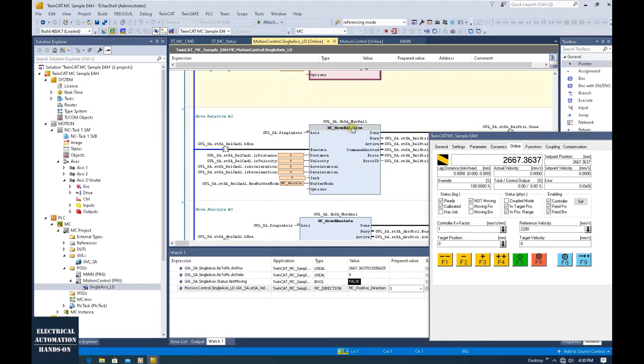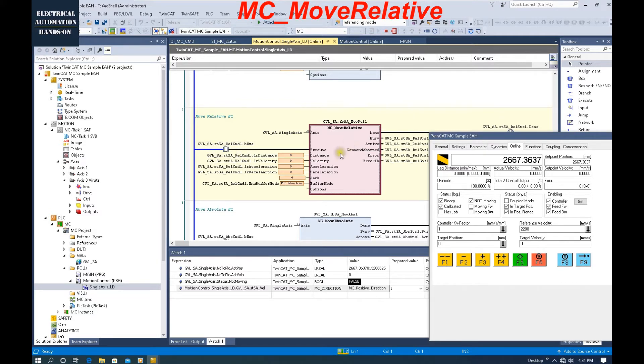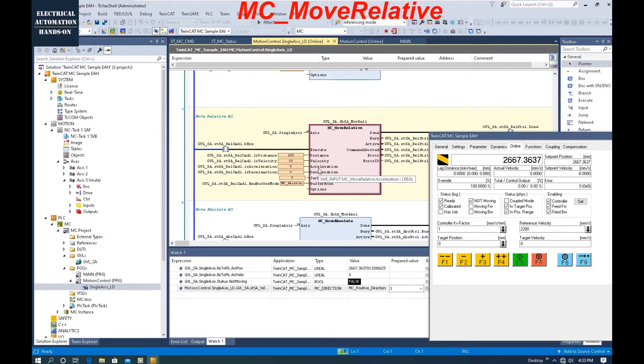Next is Move Relative. Every time we trigger this command, the axis will run a certain distance that we set here. For example, I can set 100, and the velocity I can set very low — for example, 20. Keep in mind the acceleration and deceleration: because we connect this variable, by default if we forgot to set something here, that is zero. But fortunately, in the Beckhoff system, if we set zero, that means the system will run the default setting from this axis rather than using zero directly. For some systems, leaving zero here means zero acceleration and the system won't move. To test this, I will intentionally leave zero and we will see the system still runs the axis.